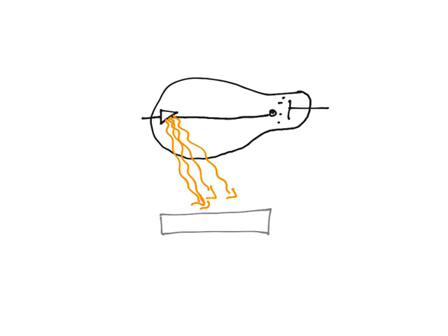And so what they wanted to do was to produce more X-rays, but there was a limit on how high this current can go. And so how can we produce more X-rays? Well, if we had more electrons to send, we'll get more X-rays out. And so they designed a new cathode, which was way more efficient in producing electrons. So of course we still have our anode over here, the positive side, wedge-shaped to direct the electrons.